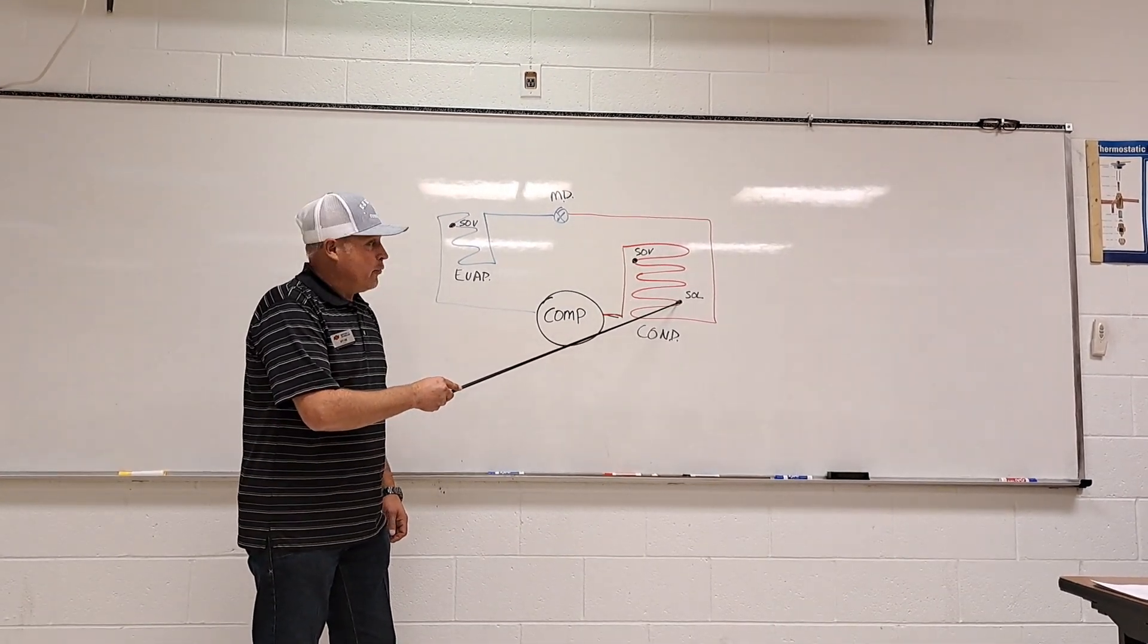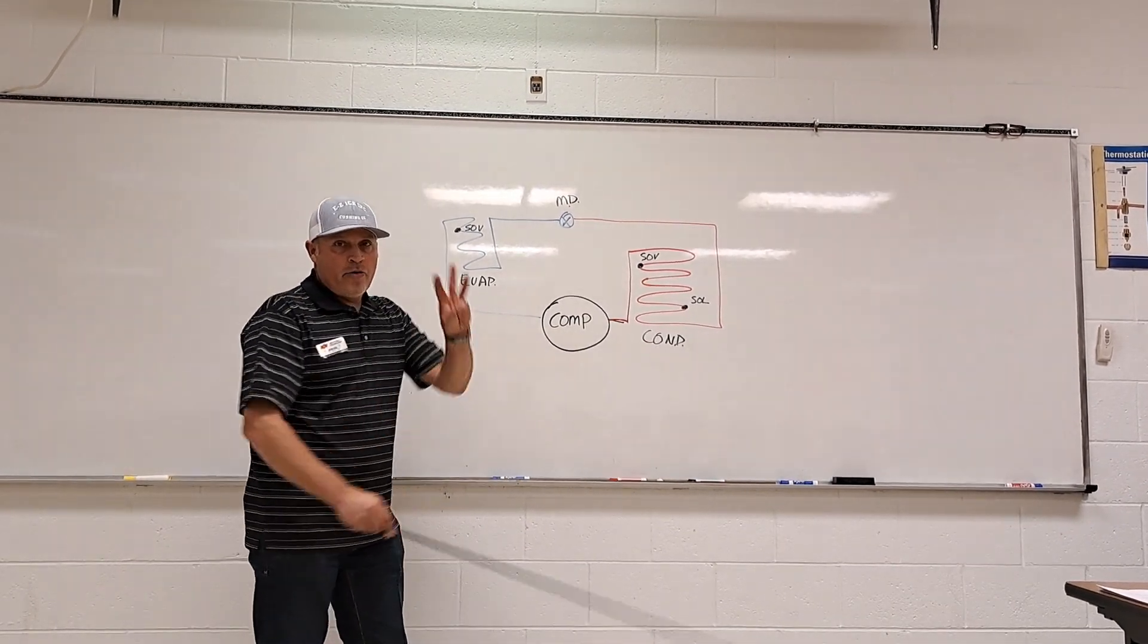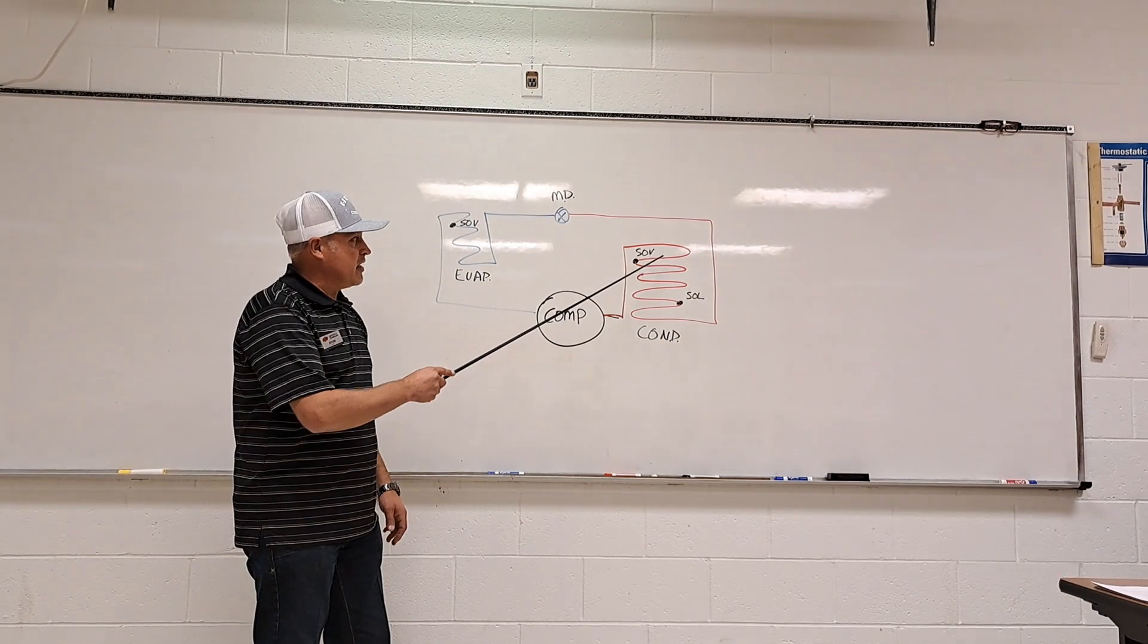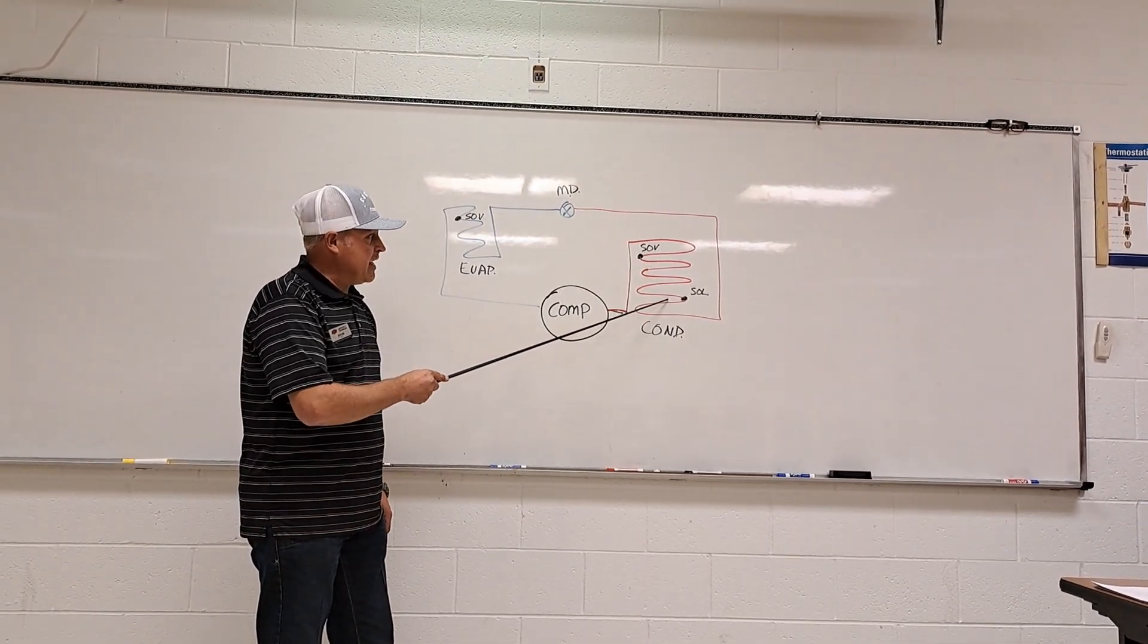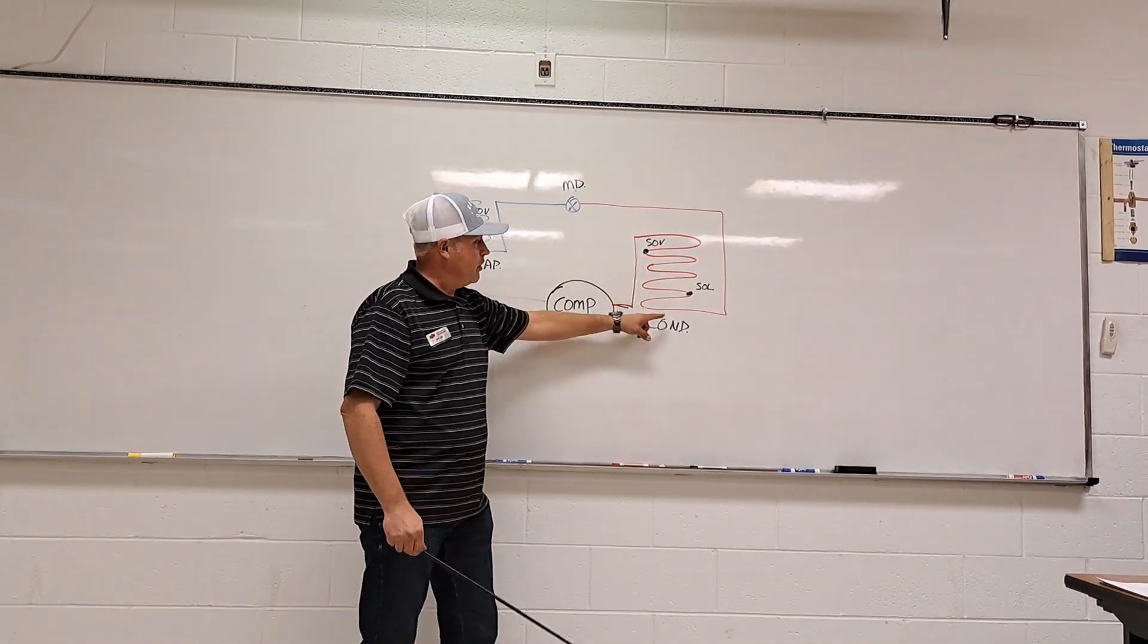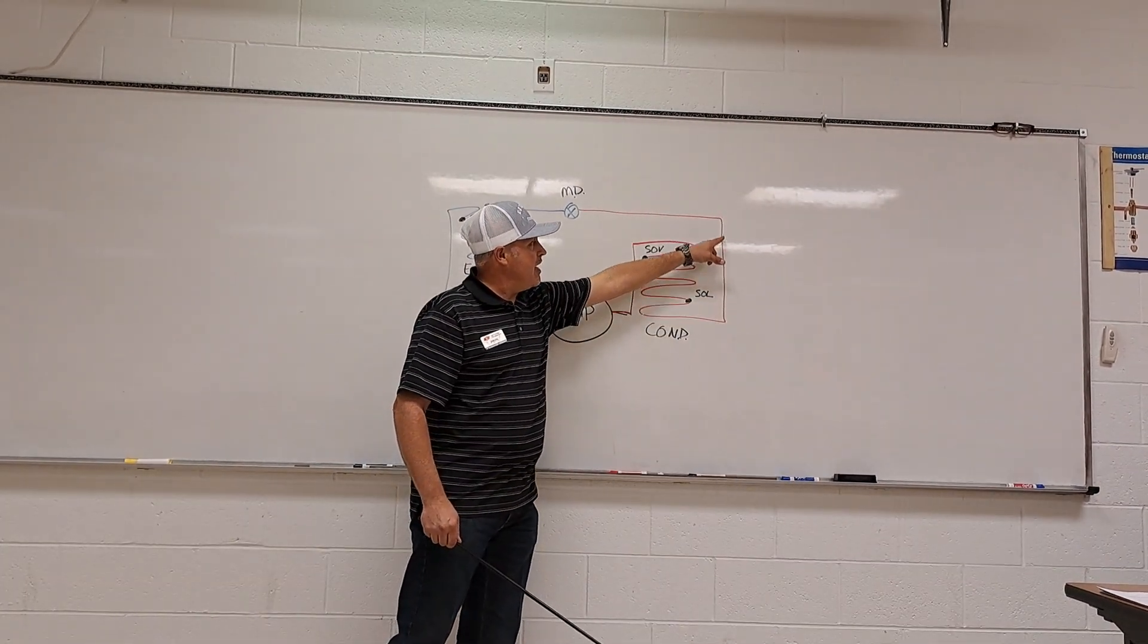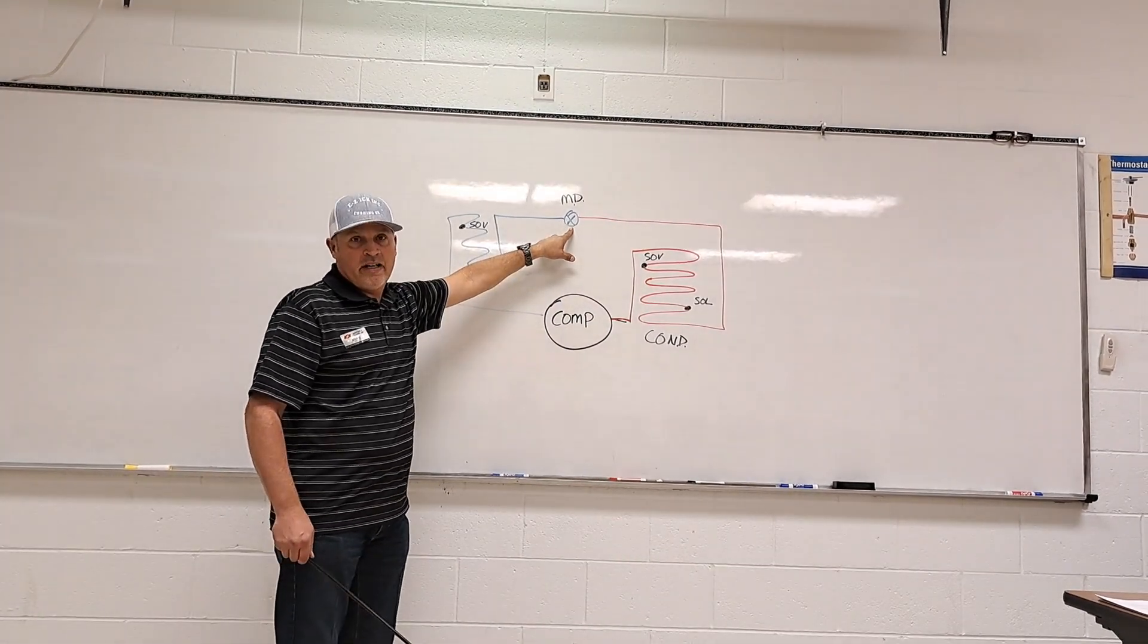We subcool out of the bottom of the condenser into the liquid line. Three things happen in the condenser: desuperheating, condensing, and subcooling. We continue subcooling through the liquid line, 100% liquid, until we reach the metering device.